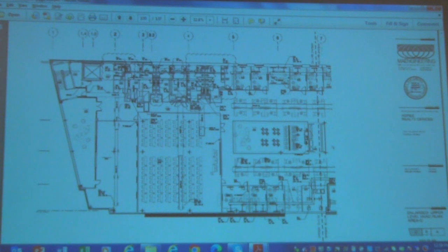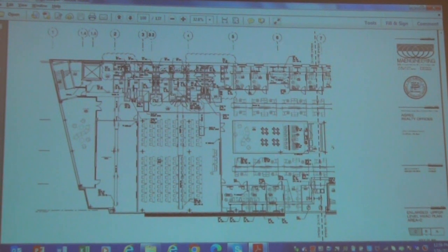Something I've noticed in the past month, and that is a lot of my plan reviews, I require what's called ventilation calculations. In the area where the engineer misrepresents the population requirement is, we're seeing a lot, it's called open offices. And I'll show you in the table just a second, but this is an example.